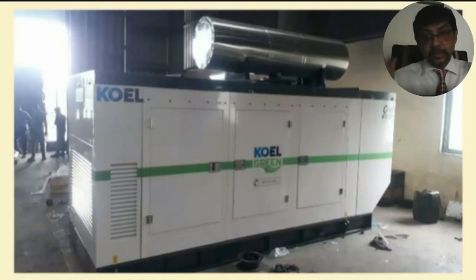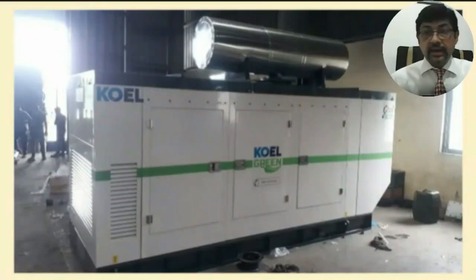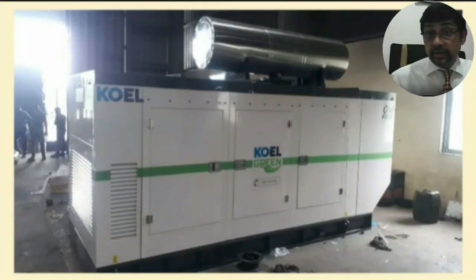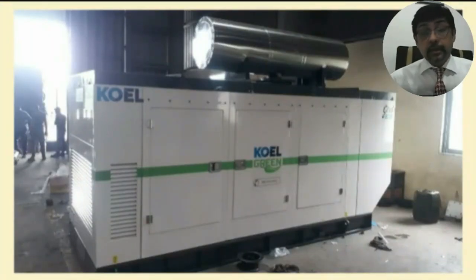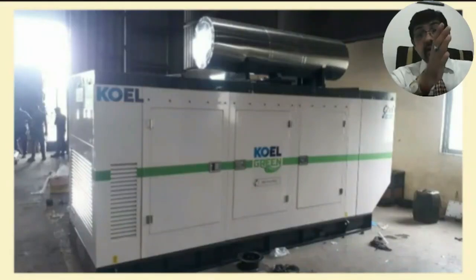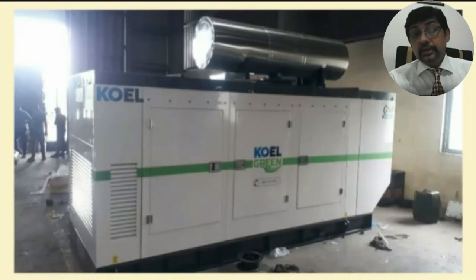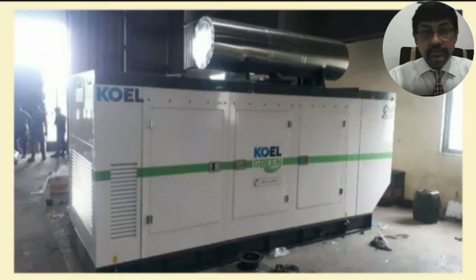Otherwise, the heat dissipated from this exhaust silencer, because the exhaust silencer is at around 450 to 500 degrees centigrade. This is the temperature of the gases coming out of the generator. So inside the silencer you have gases passing at 450 to 500 degrees centigrade, and the thermal heating is going to affect the efficiency of the generator. That is the reason the aluminium cladding is done on the silencer. Yeah, next. The same, yeah, next.